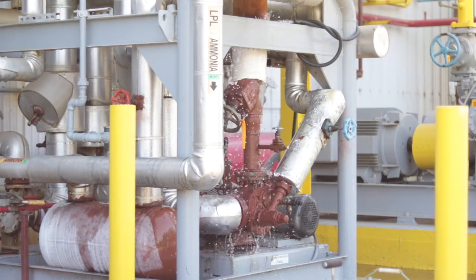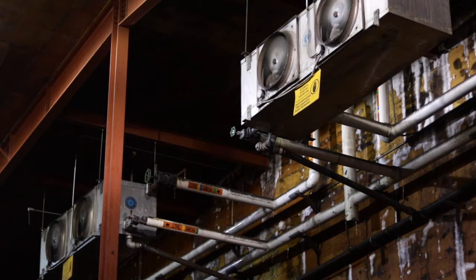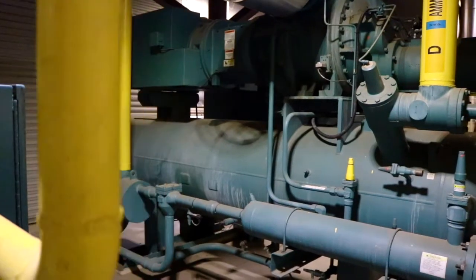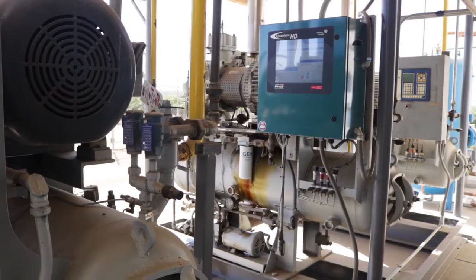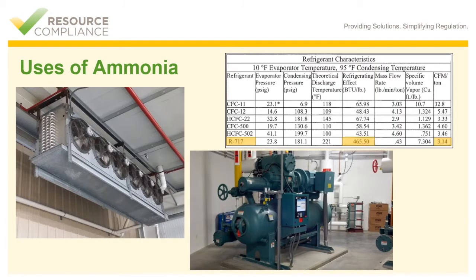Probably the largest part of my audience is familiar with ammonia as a refrigerant. We cannot move on without mentioning the use of anhydrous ammonia in industrial refrigeration. Anhydrous ammonia is a very environmentally friendly and efficient refrigerant. As you see in the table on this slide, R717 is the refrigerant designation for ammonia. Its refrigerating effect — the BTUs per pound, or heat transfer per pound of refrigerant — is significantly higher compared to any other refrigerants listed on this slide.